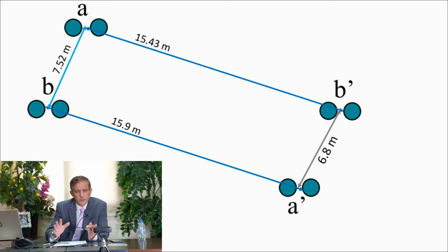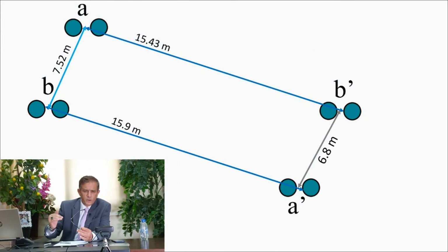I always start from the last station, and don't follow the typical examples. I need three spacings: between AB, BC, and CA. If I multiply them together to the power of 1/3, this is the geometrical mean distance. For AB, I took the circuit of AB, and these are the spacings that you can see. For any spacings, not only conductors, even houses in a city, the geometrical mean distance is their multiplication to the power of 1 over their number.